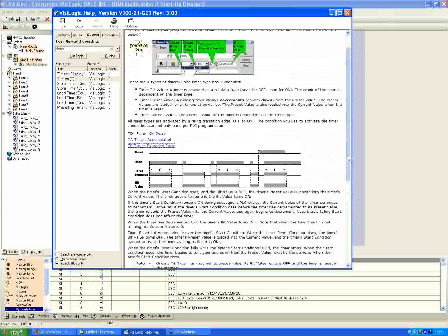I can say real quick, just to summarize, the TD timer, basically it'll always reset back to the preset time, and there's no manual reset required. So when it counts down, it's just going to hop back up to the next preset time automatically, and you don't have to manually reset it. The TA timer, this one will pick back up from the previous current value. So if you stop sending a condition, a power flow to the timer, if you break that in the middle of the countdown, it's going to automatically pick back up from the previous current value and continue to count down from that previous value.